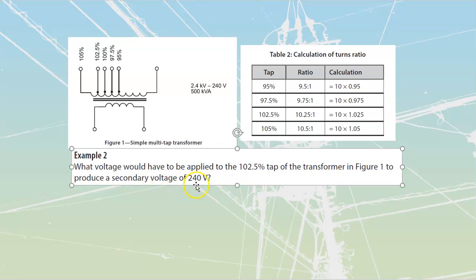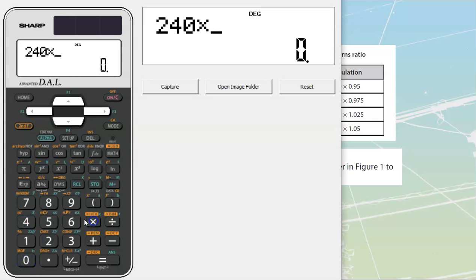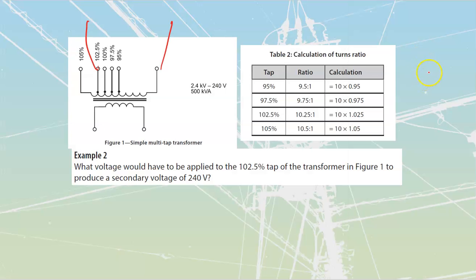If I need to produce a secondary voltage of 240 from the 102.5% tap, I'm just going to figure out what that multiplier would be. Once again, 102.5% tap times 10 to 1 gets me to 10.25. So 240, I can just multiply by 10.25. Gets me to 2460. That's just a little bit higher than the rated 2400, which makes sense, the way they've got that one laid out. Poorly worded question because, once again, we have an existing voltage and we always adapt to the existing voltage, not that we have a transformer and force the voltage to adapt to that.